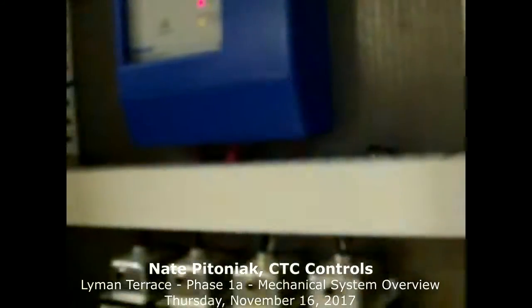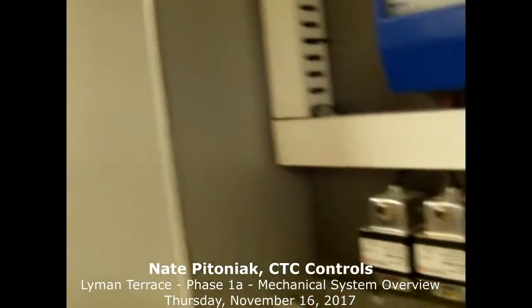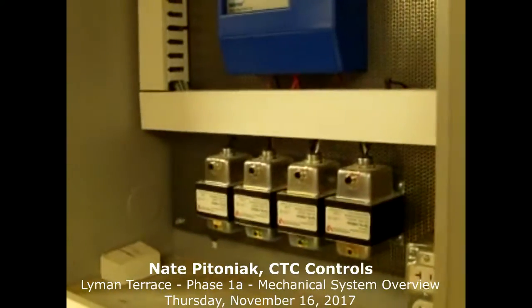But just for the people who are not so into this like you guys are, when you say these transformers are for the baseboards, you're really saying these transformers are providing power for the zone valves in the baseboards. Correct. So it's the zone valve that's opening and closing by direction of the thermostat in the space, and these transformers give those zone valves the power to do that. Correct, and another good indicator that a transformer has tripped is if you go up into the space and the thermostat itself is dark, no power to it. That's a good indicator you have a transformer problem, because they're not battery operated. They're pretty neat.